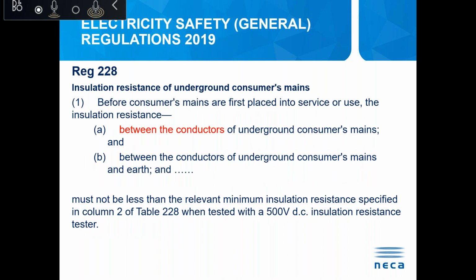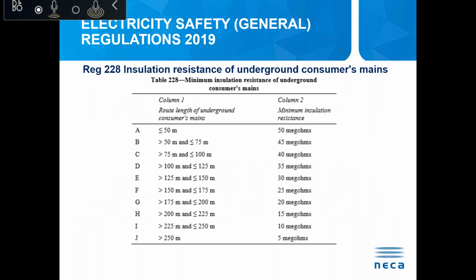Some of the main changes: insulation resistance of underground consumer mains. Previously, all testing had to be done and you just needed a minimum of 1 meg ohm insulation resistance for all undergrounds. Now they've taken the table out of the service and installation rules, and depending on the length of the cable, up to 50 metres, you must have a minimum of 50 meg ohms. And greater than 250 metres on a new installation has to have 5 meg ohms of insulation resistance.